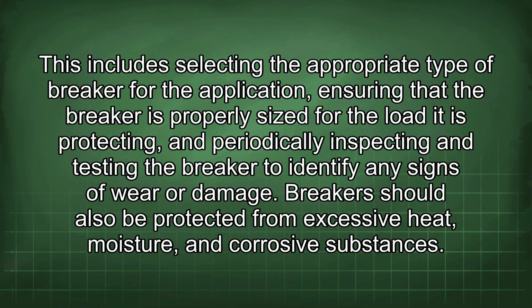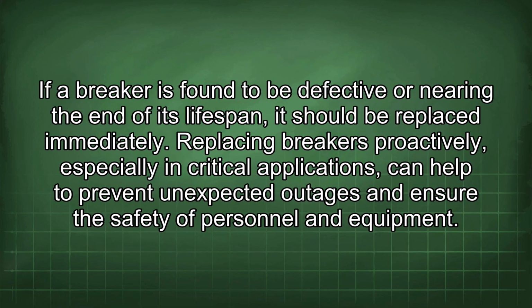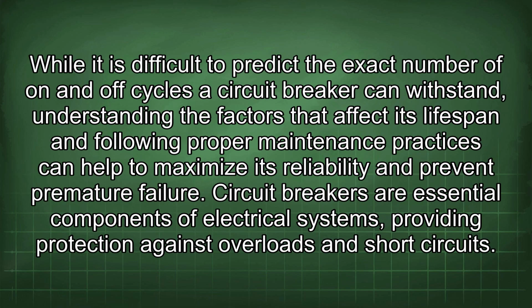Breakers should also be protected from excessive heat, moisture, and corrosive substances. If a breaker is found to be defective or nearing the end of its lifespan, it should be replaced immediately. Replacing breakers proactively, especially in critical applications, can help to prevent unexpected outages and ensure the safety of personnel and equipment.